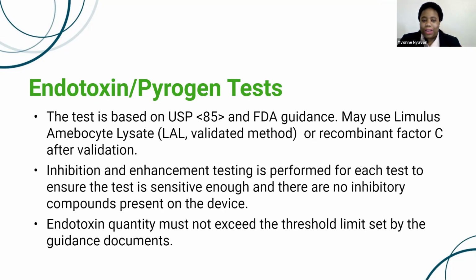So the RFC method can also be validated for a sample, especially if someone is very interested in using that just to protect the horseshoe crab population. So that's an option now as well. And inhibition and enhancement testing is typically performed for each test to ensure the test is sensitive enough and there are no inhibitory compounds present on the device. And then the endotoxin quantity must not exceed the threshold limit set by the guidance document.